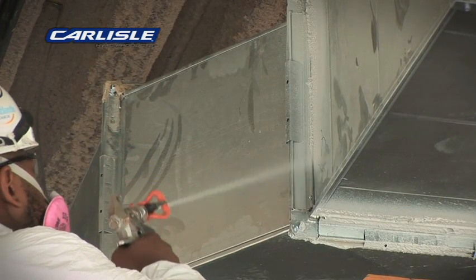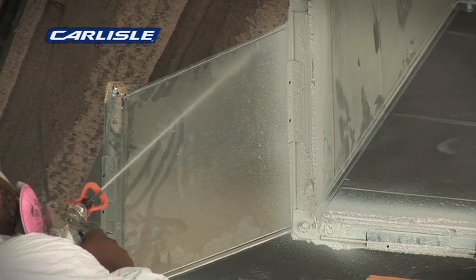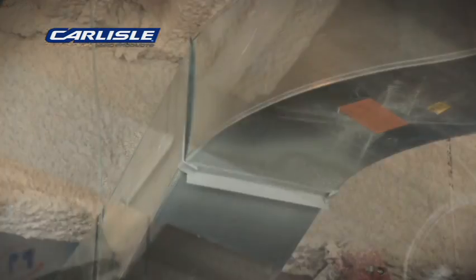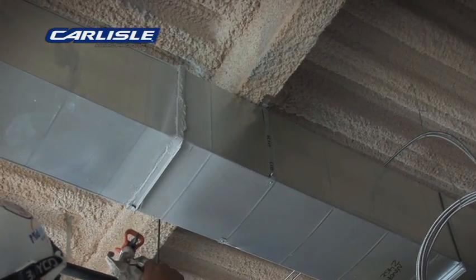One of the things that was driving the cost of our projects associated with duct sealant was that we were eliminating slip and drive joints because they leak so much more than a TDF or a duct mate joint. By using this product, we can go back and we can put slip and drive back into our criteria, which is within the SMACNA criteria. And we're able to seal it and achieve virtually zero CFM loss during our duct tests.